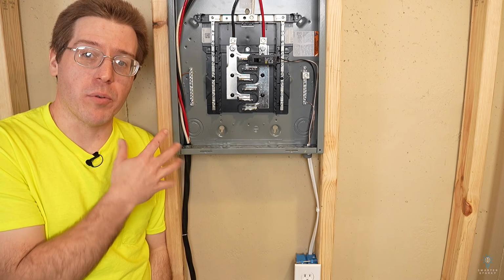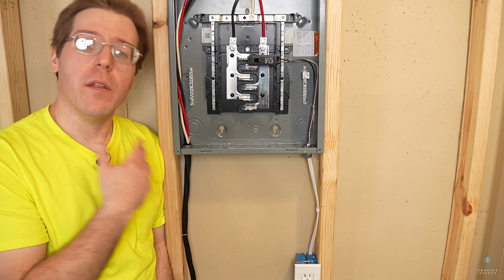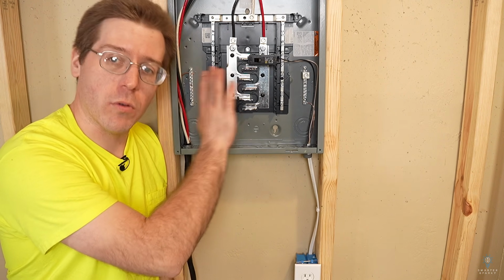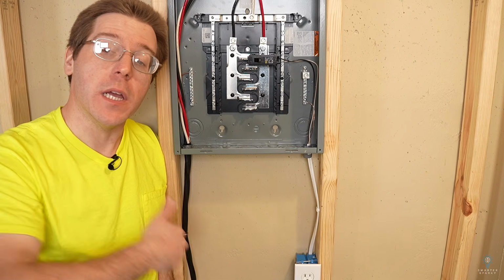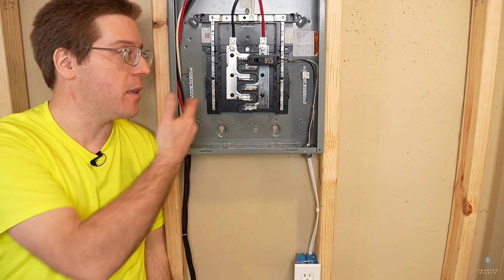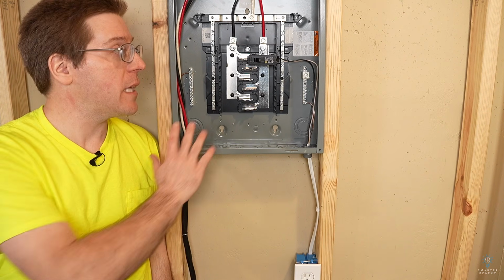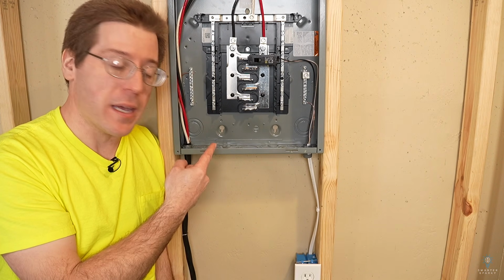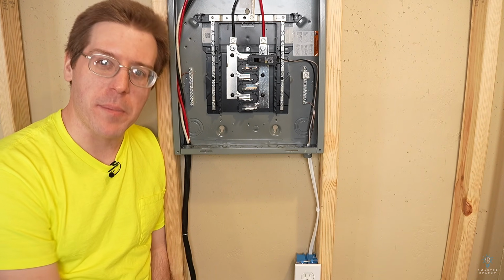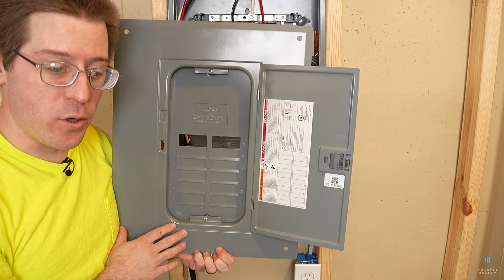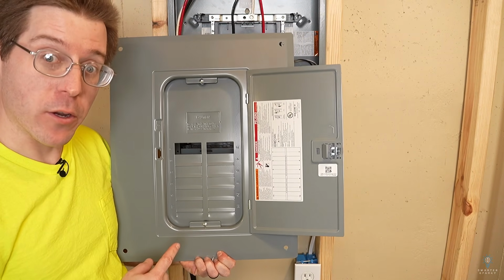And that's how we run a branch circuit off of a sub panel. The only real difference is grounds are separate from the neutral. In the main panel, you can share them. In the sub panel, they are separate. So let's get the dead front on this, fire this panel up, check that outlet, and wrap up this video. So this is a brand new panel, and it came with a brand new panel cover.